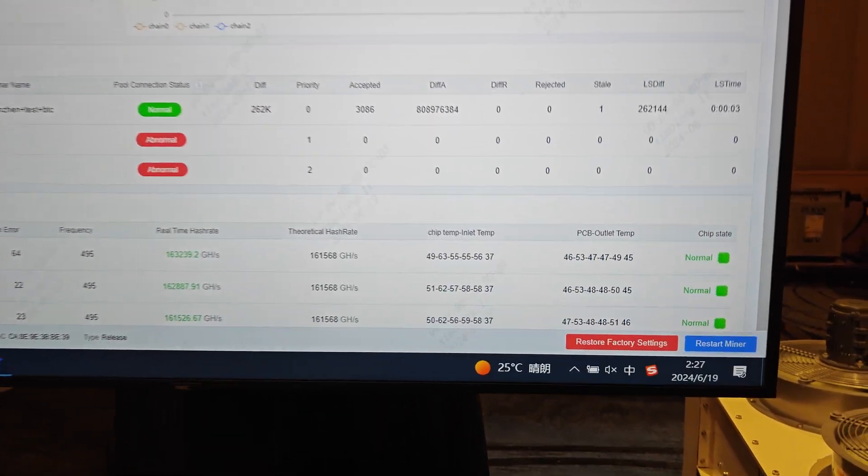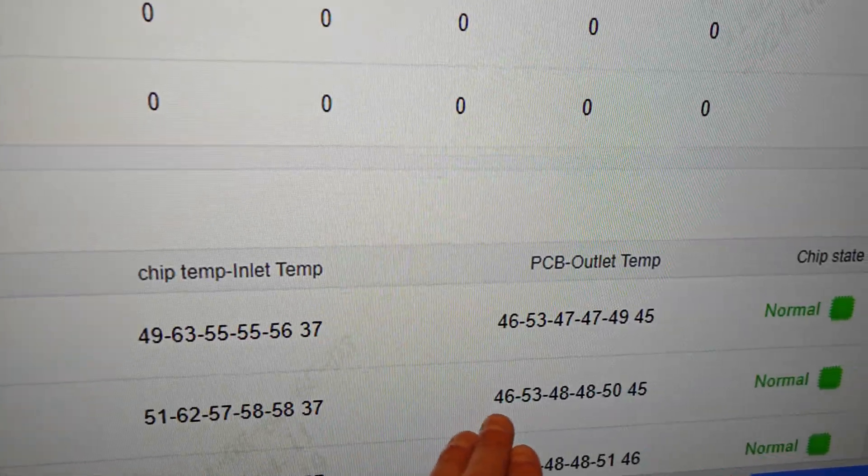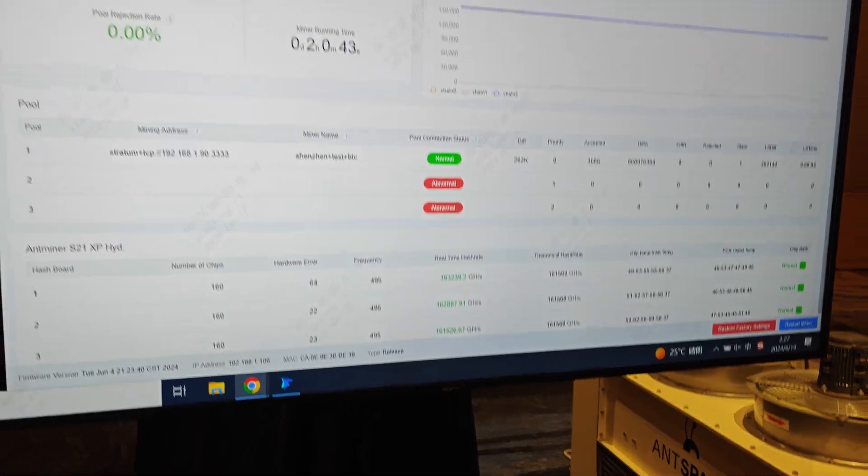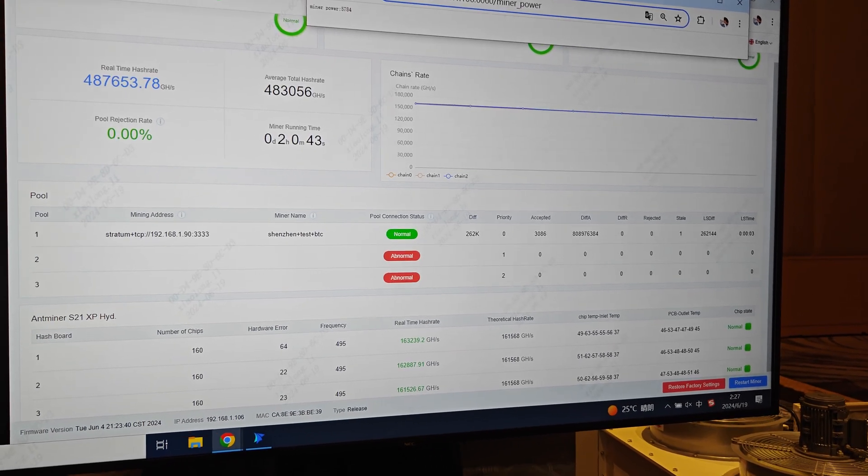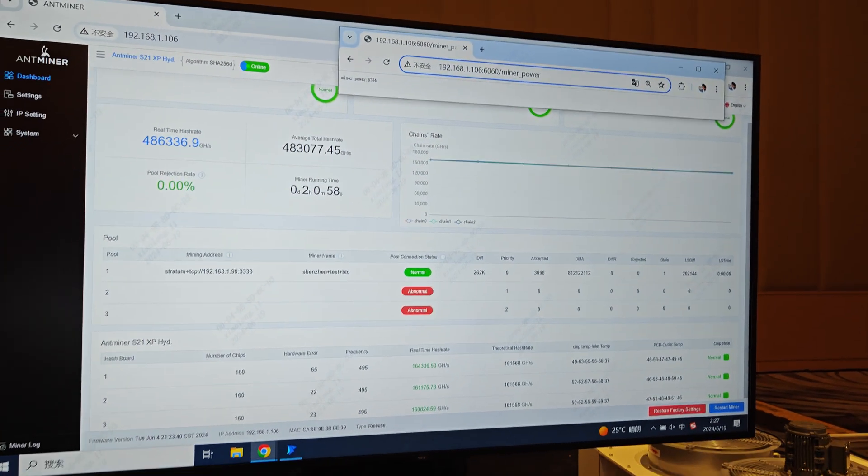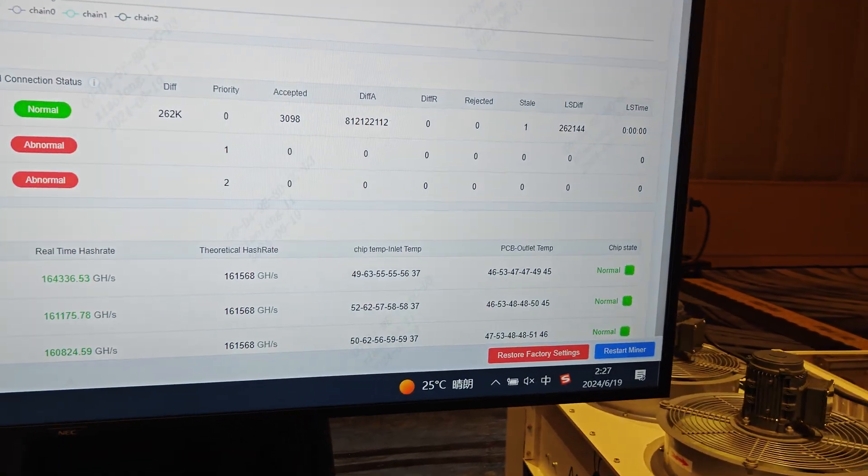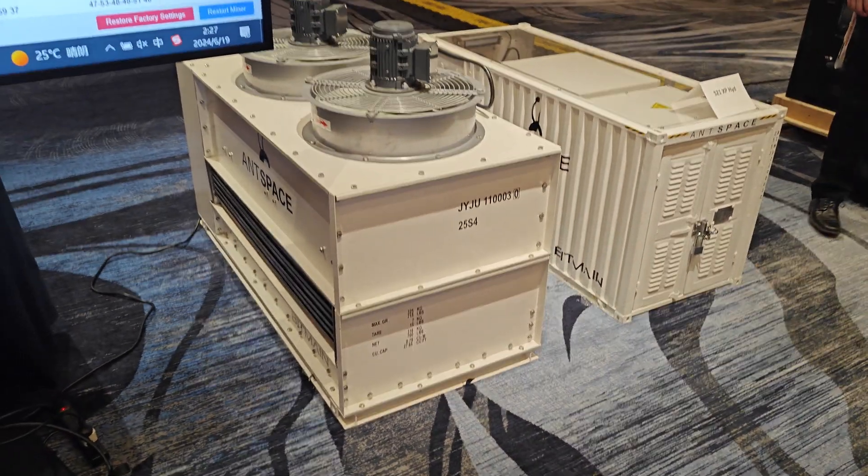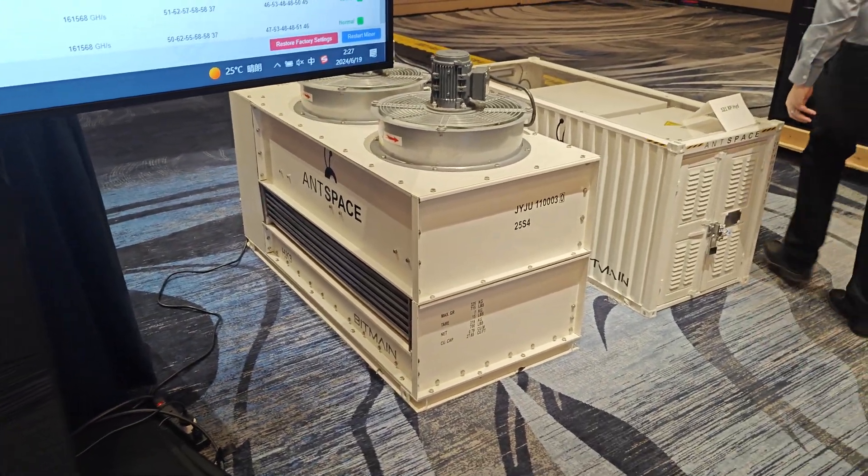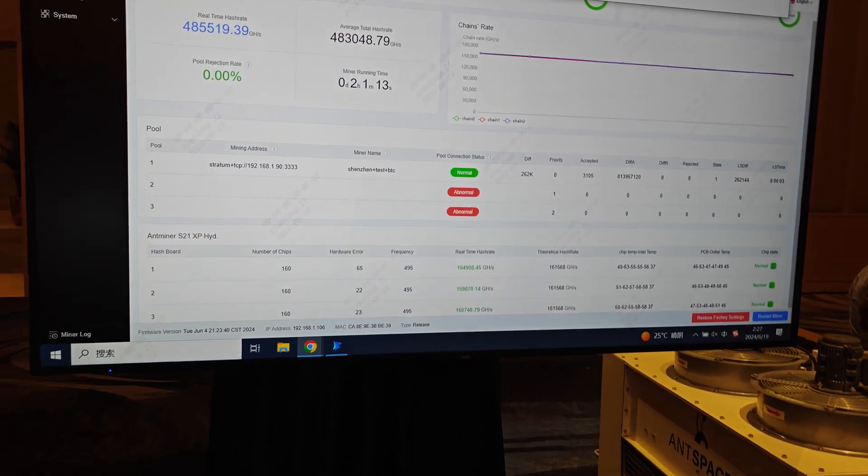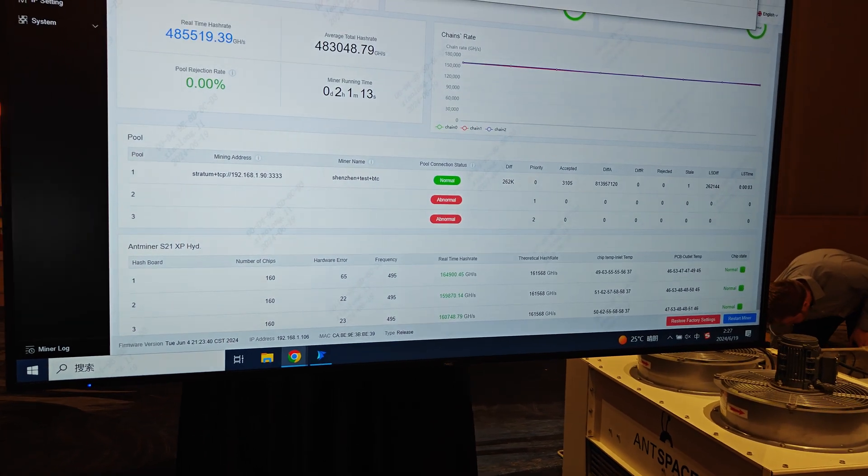Also, they're being cooled at such great results here. You can see that. Now, talking with them about cooling, because you might be guessing, like, what about cooling in hotter environments? Like, how much efficiency are you losing? So we talked to them about that. And the maximum dry coolers can pass through. The maximum they can produce or put out good performance is when the ambient temperatures outside are less than 90. Basically, like 80, 90. So you don't want to go higher than that.